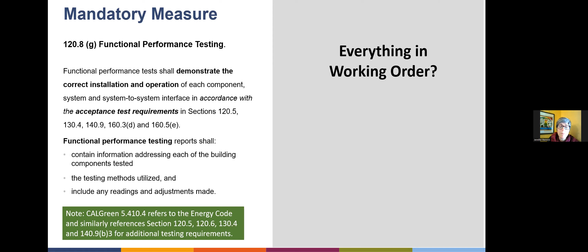It includes some of the process, but new to the code cycle is section 160.3 and 160.5. That has to do with the common spaces in multifamily mixed use projects. So since there's a whole new code section for multifamily, there's now a new part, a new reference under those mandatory measures of what areas have to have the functional performance testing.